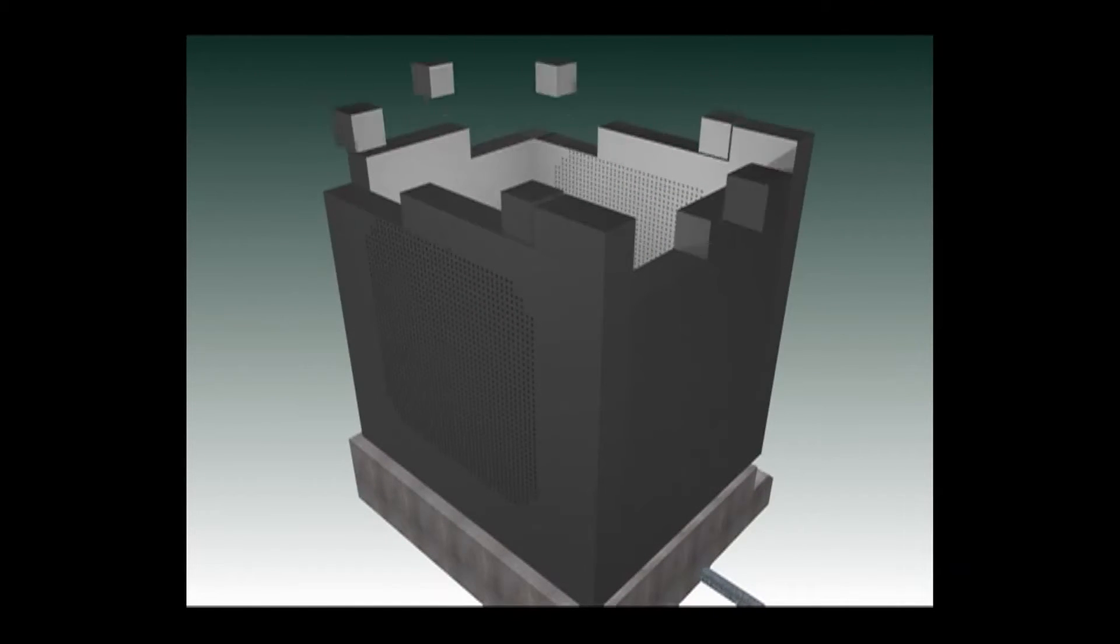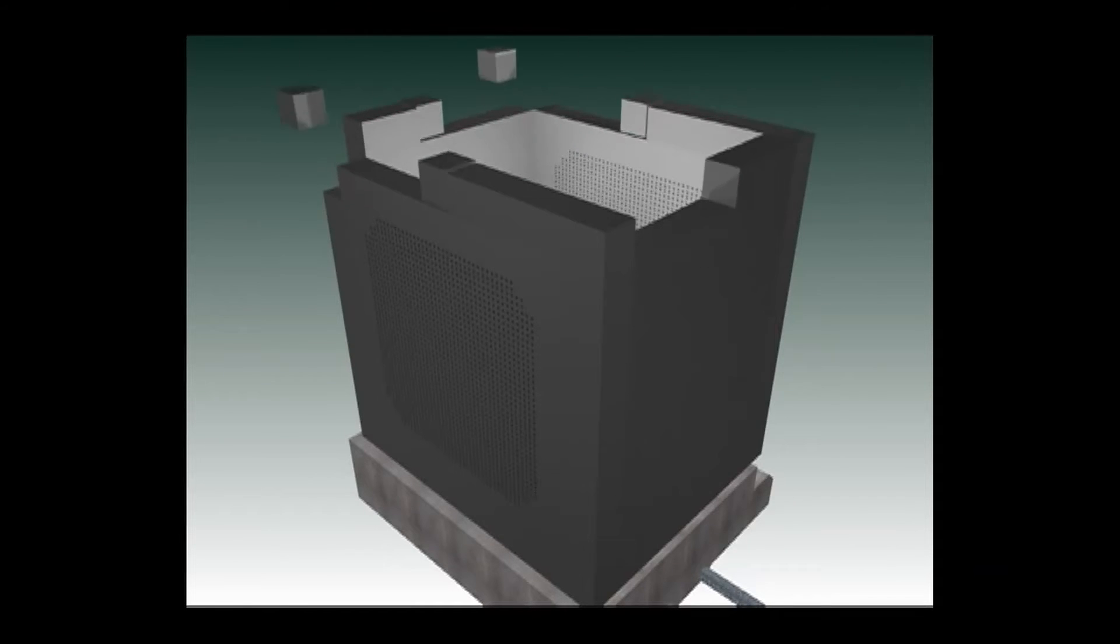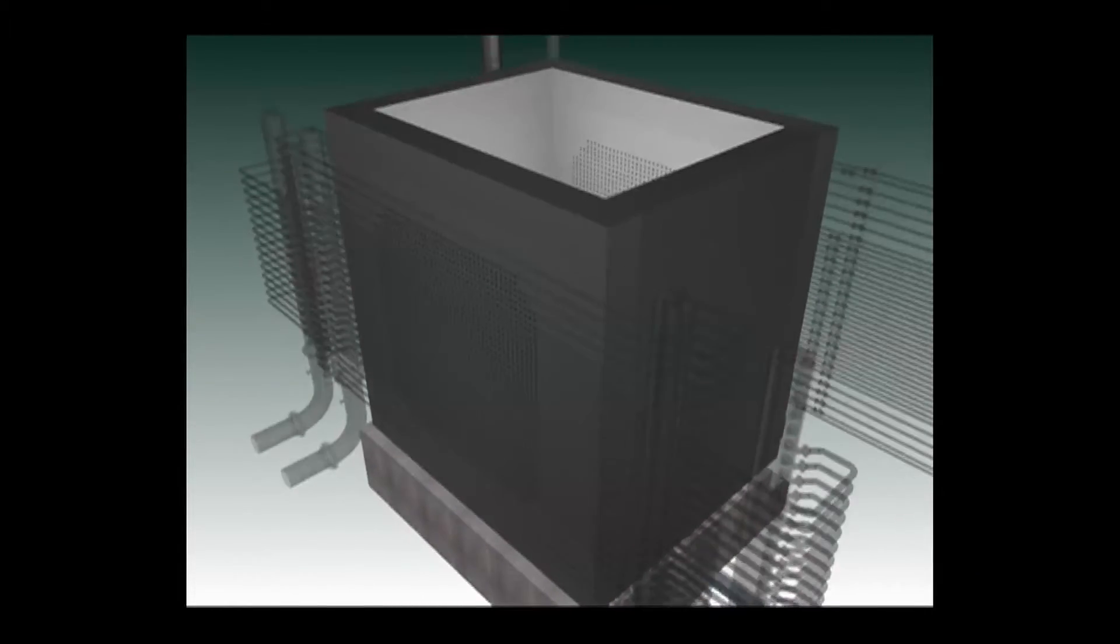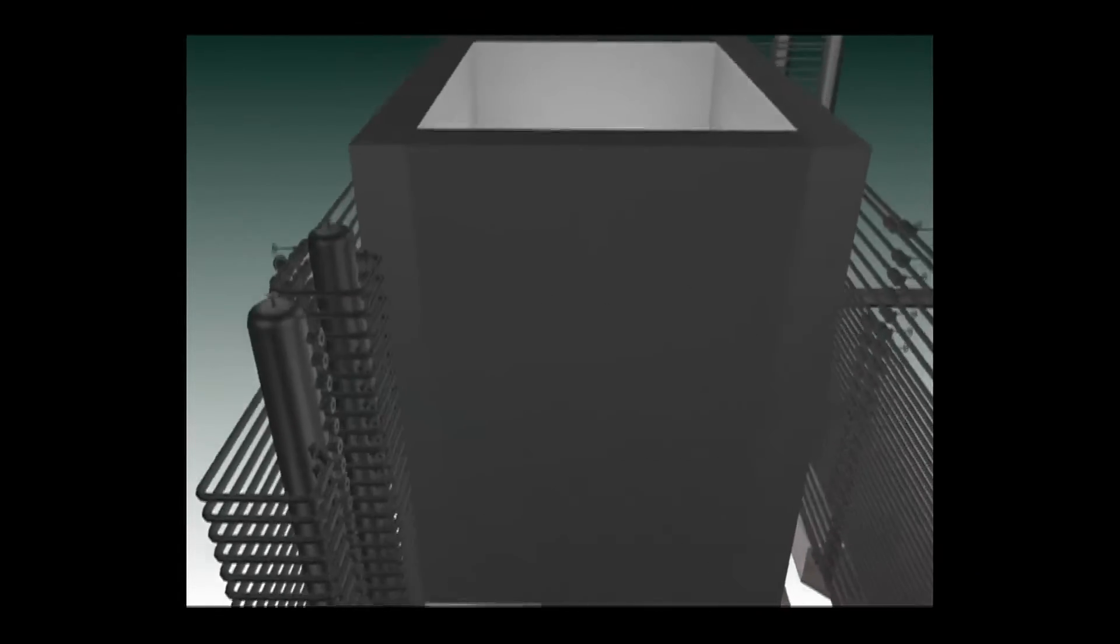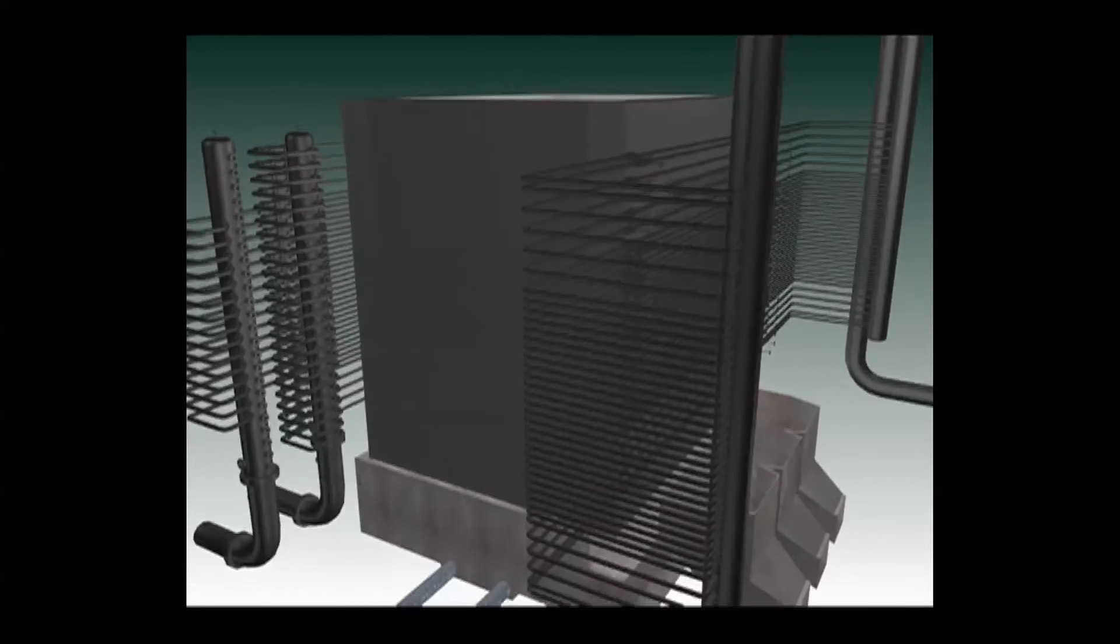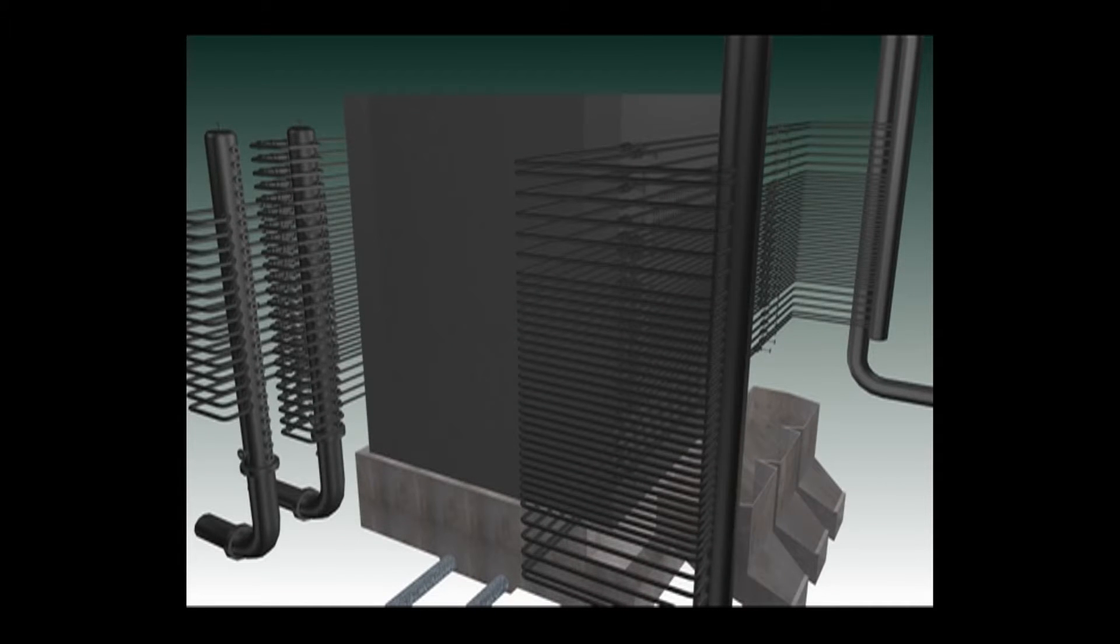While the shield walls are being completed, the enormous piping system to deliver the required 30,000 gallons per minute of cooling water was put in place. The water from the pump house next to the reactor building arrives at the reactor front face through two 20-inch diameter risers on each side. 4-inch diameter cross-header pipes connect to the risers and run under each of the 46 rows of process tubes.